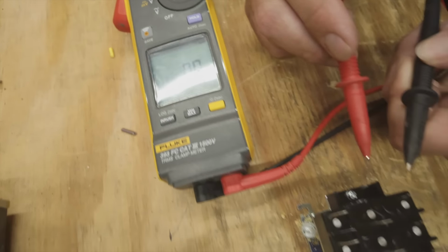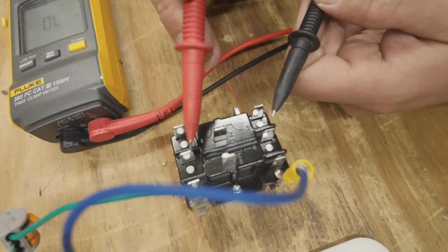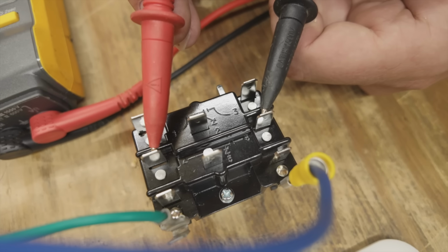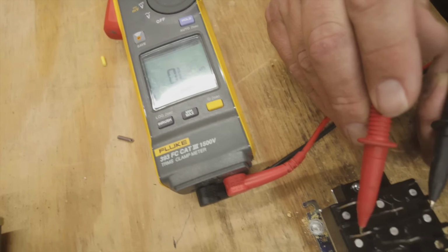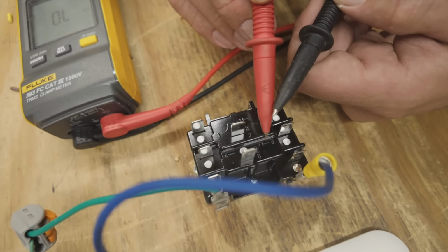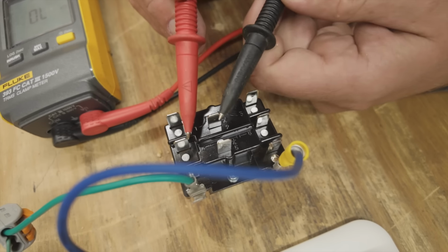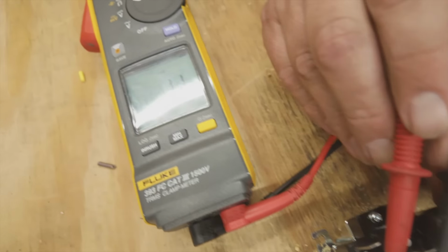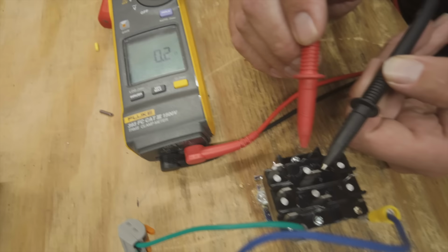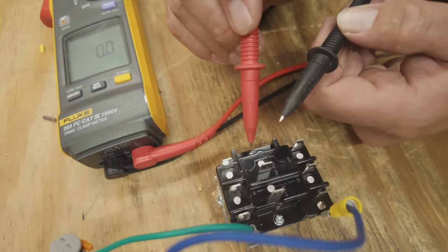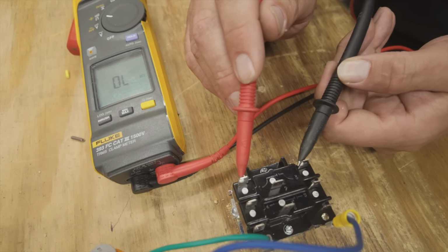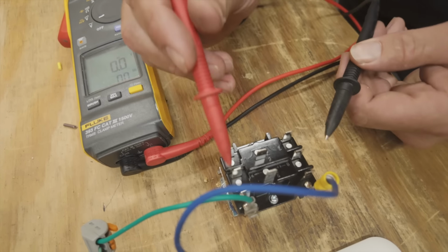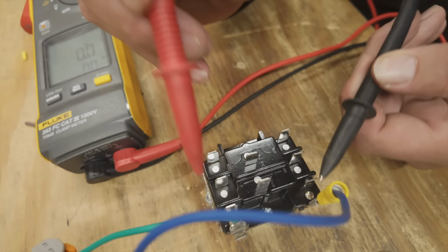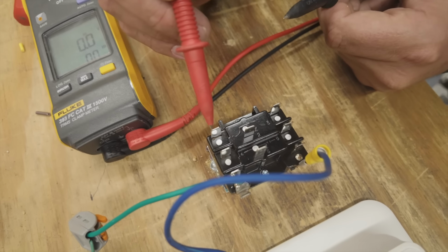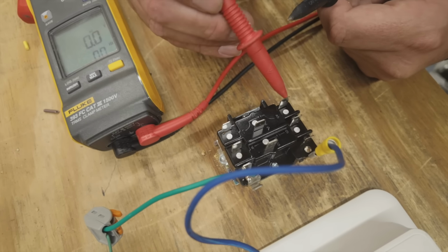But from 1 to 2, it's normally closed. So right here, complete circuit, all right? I'll show you the next one. The next one is from 4 to 6, it's normally open. So there's nothing, it's OL. And then 4 to 5, it's normally closed. So completed circuit. So now you can see from 4 to 5, it's closed. 1 to 2, it's closed. But from 4 to 6, it's open. And 1 to 3, it's open. Whenever we receive voltage here, which we don't have now because we don't have a call, then 4 to 5 will open, 1 to 2 will open, but 1 to 3 will close.